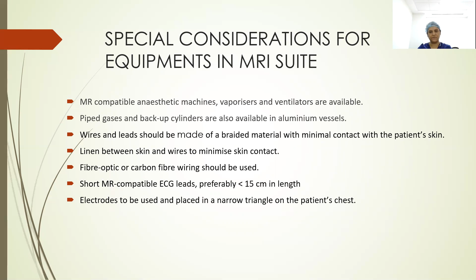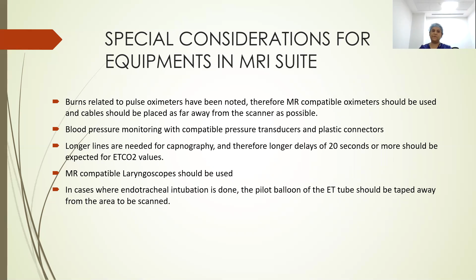Burns related to pulse oximeters have been noted. Therefore, an MR-compatible oximeter should be used and cables should be placed as far away from the scanner as possible. Blood pressure monitoring is done with compatible pressure transducers and plastic connectors. Longer lines are needed for capnography, and therefore we must anticipate delays of about 20 seconds or more for the expected EtCO2 values. MR-compatible laryngoscopes should be used, and in cases where endotracheal intubation is done, the pilot balloon of the ET tube, which has a small ferromagnetic spring, should be taped away from the area to be scanned.